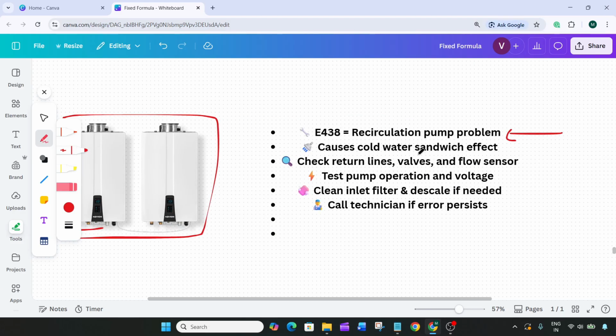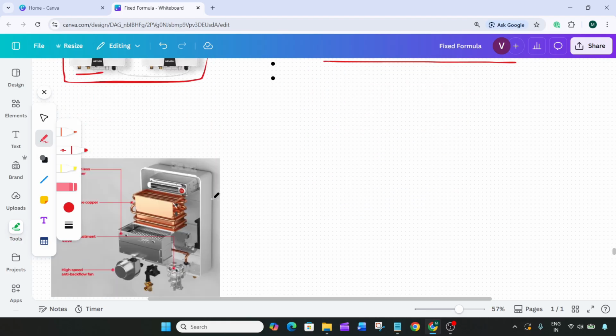The cold water sandwich happens when the heater has been idle. The hot water sitting in your pipes cools down, and when you turn on a faucet, that cooled water comes out first. Navien's recirculation system and buffer tank are designed to prevent this by maintaining warm water in the lines. But if the pump fails or circulation is interrupted, the system triggers the E438 code.